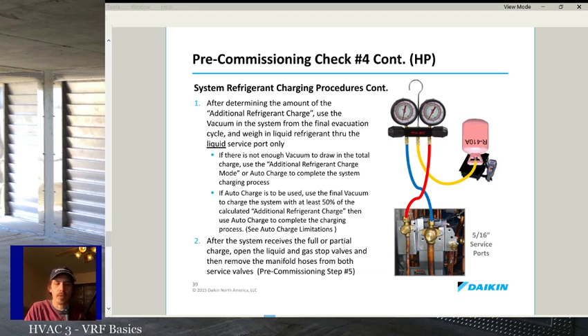I charge by weight every time and almost never have to adjust it. And if I suspect problems in the system, I will pull most of the charge out, not enough to have to pull a vacuum on the system, but I'll pull most of the charge out till I get down below 10-20 psi. By the time you get there, you've got almost all the refrigerant out anyway. Get it down to about 10-20 psi, then weigh it all back in, and I know I got the right charge in it. I charge by weight.